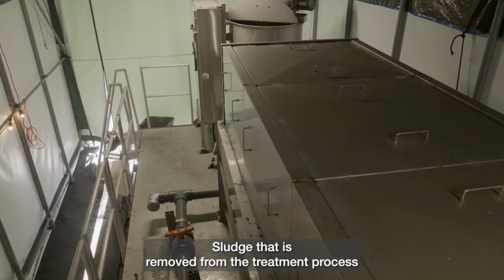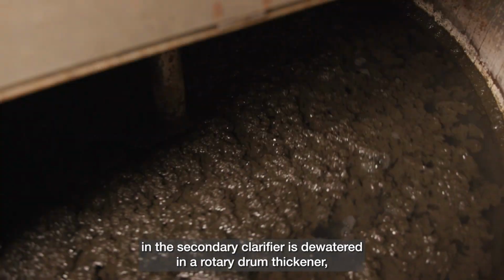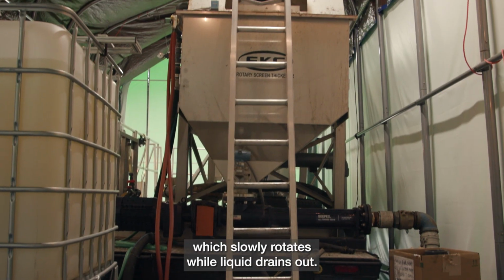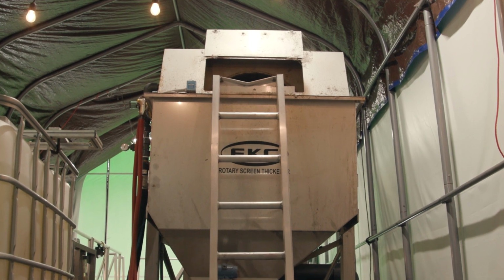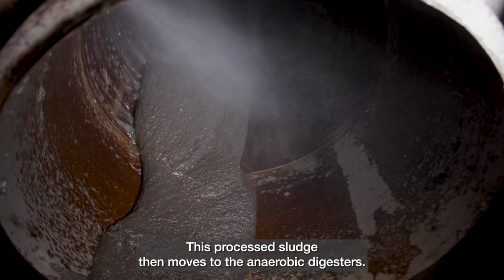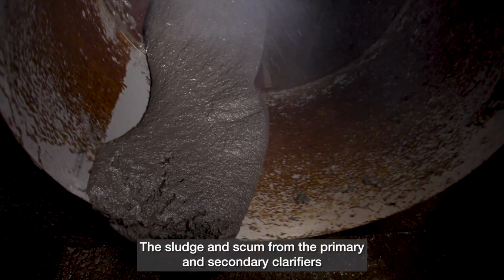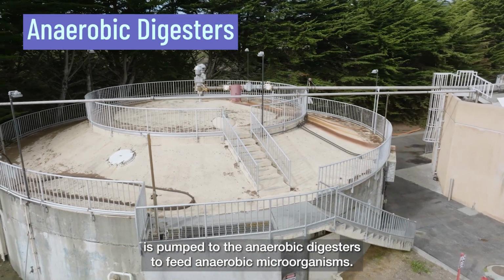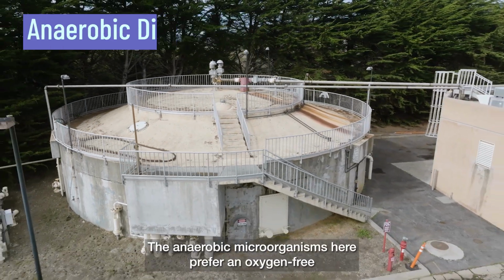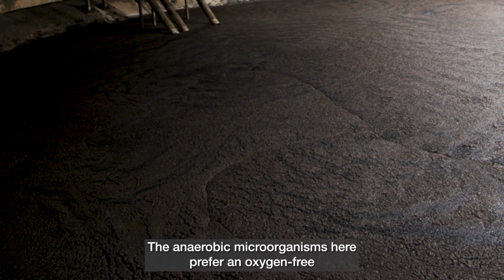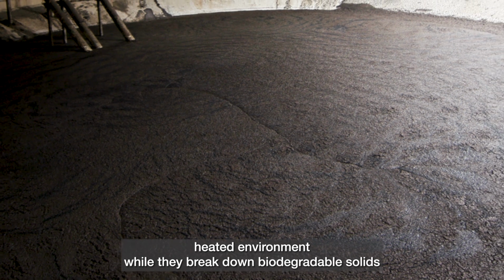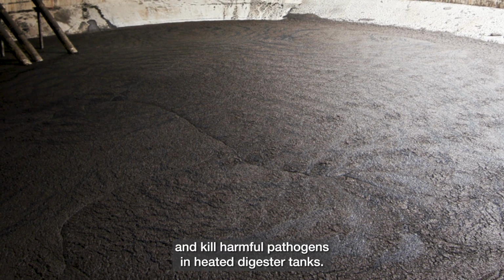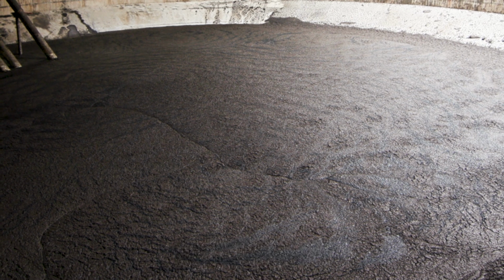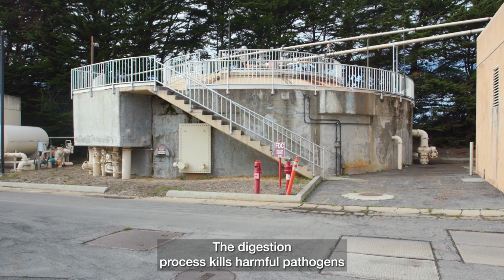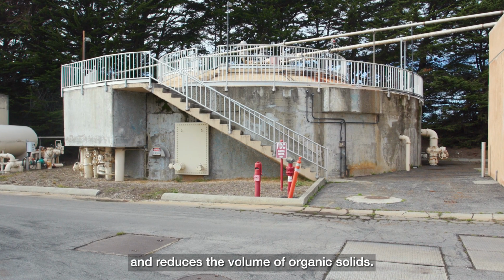Sludge that is removed from the treatment process in the secondary clarifier is dewatered in a rotary screen thickener, which slowly rotates while liquid drains out. This processed sludge then moves to the anaerobic digesters. The sludge and scum from the primary and secondary clarifiers is pumped to the anaerobic digesters to feed anaerobic microorganisms. The anaerobic microorganisms here prefer an oxygen-free, heated environment while they break down biodegradable solids and kill harmful pathogens in heated digester tanks. The digestion process kills harmful pathogens and reduces the volume of organic solids.